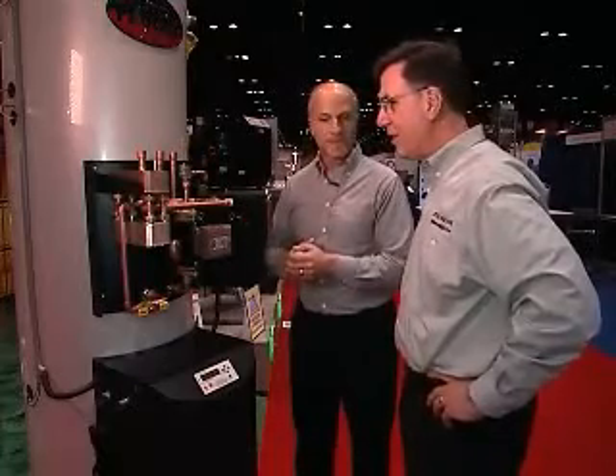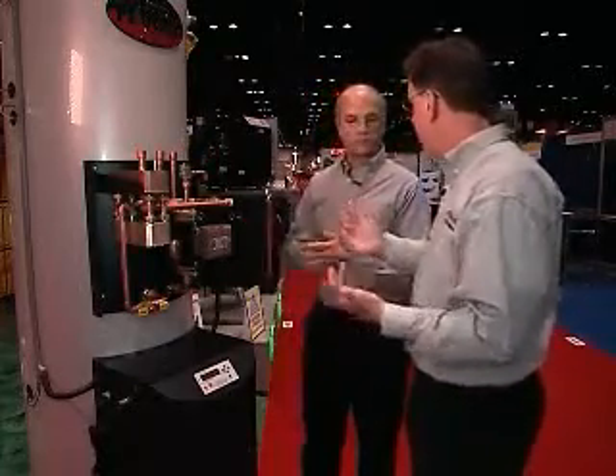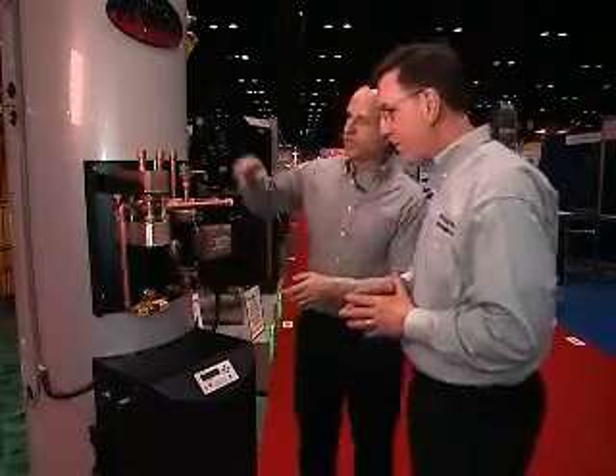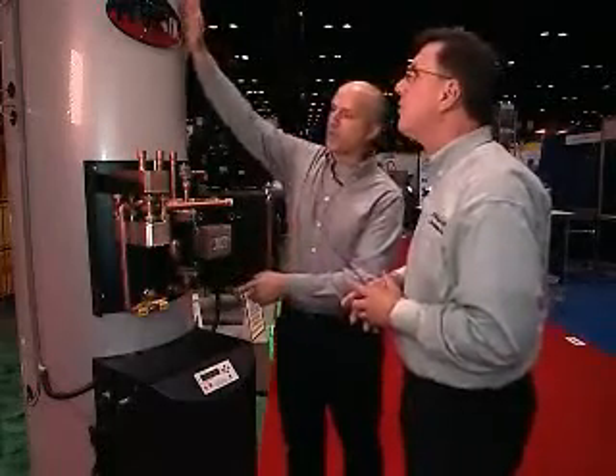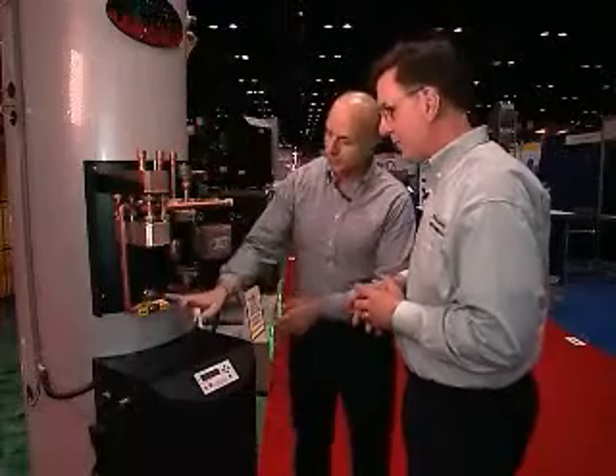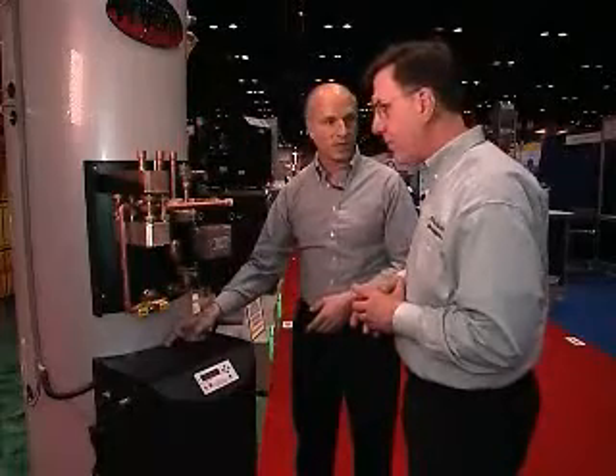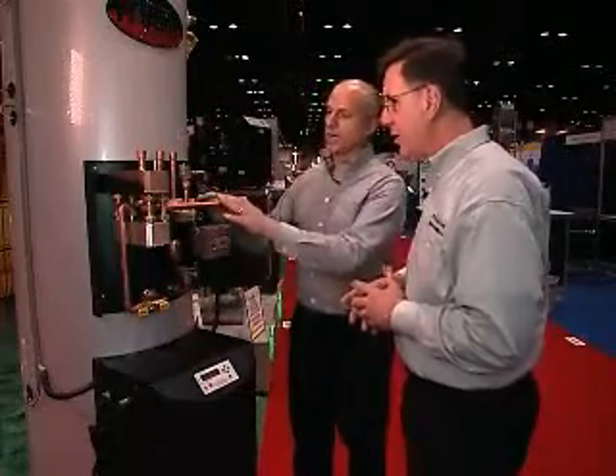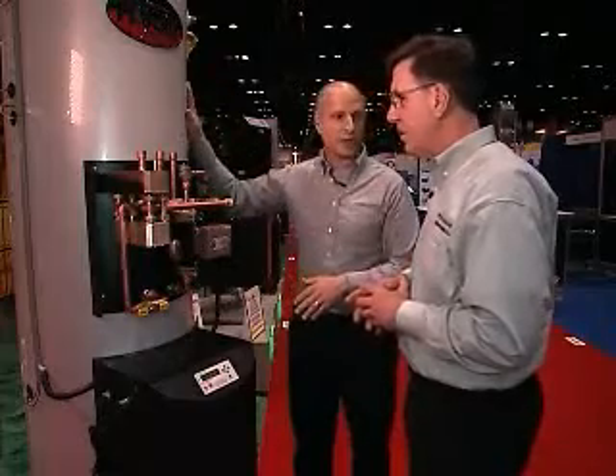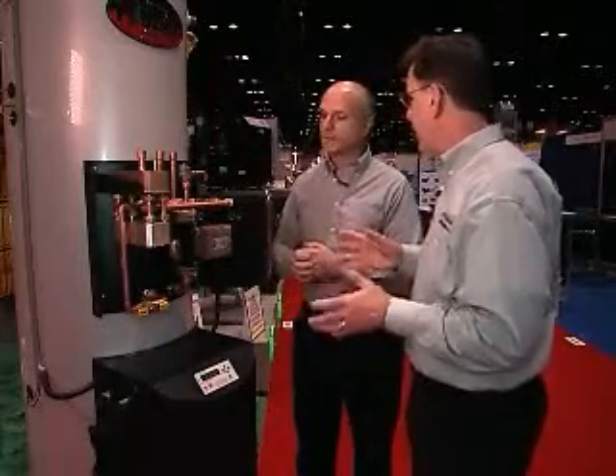I like it. And there's no cross connection between the water? No, there's not. There are dip tubes in here where we're drawing the water from the top through the heat exchanger and then delivering it back down to the bottom of the tank. Okay, so we're isolating the hydronic loop from the domestic water in the system. So no worries about Legionnaires or anything like that?